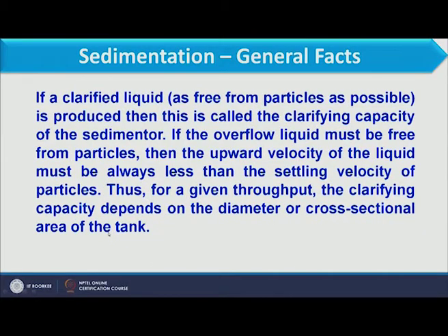If the overflow liquid must be free from particles, then the upward velocity of the liquid must always be less than the settling velocity of the particles. And thus, for a given throughput, the clarifying capacity depends on the diameter or cross sectional area of the tank.